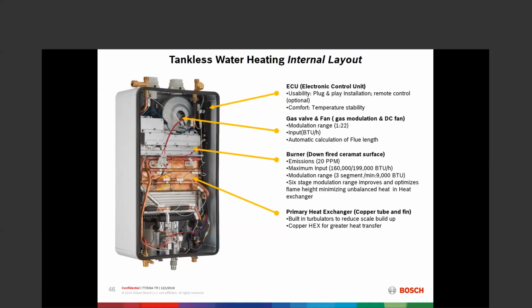Typically what destroys a copper heat exchanger is the formation of condensate inside of that combustion chamber. And with our combustion technology, we're not getting that. That's not going to happen. Also, for durability, built into the combustion chamber heat exchanger on the waterway, as the water's moving through the copper tubing, it has what we call turbulators. Those turbulators are designed to ensure that we are disrupting the laminar flow of water through the unit so that we get even heating and we diminish or minimize scale buildup.